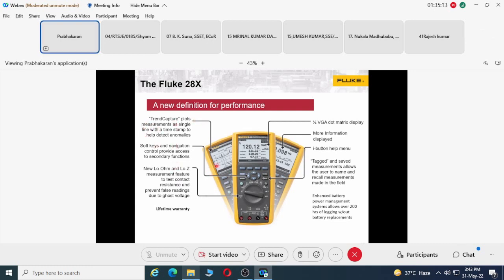That is, if you want to capture the output of a sensor as a graph, or see multiple parameters at once like frequency and current, or minimum, maximum, and average of a measurement, all those things you can get on one screen. We recommend this for very specific work like electronic maintenance or troubleshooting, where you get much more features. For field applications it may be slightly an overkill, but for laboratory applications where you really want to do troubleshooting, this will be a better choice.